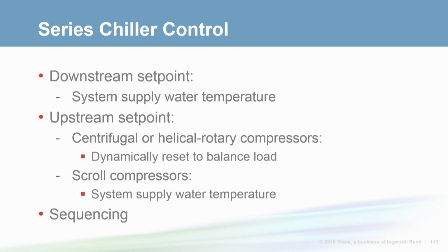Simply start the chiller that's most efficient, and once a pair of chillers are running, start and stop chillers in pairs from then on. Our next and last question today is, compared to operating 1 pump, will operating 2 pumps at lower speed save energy?